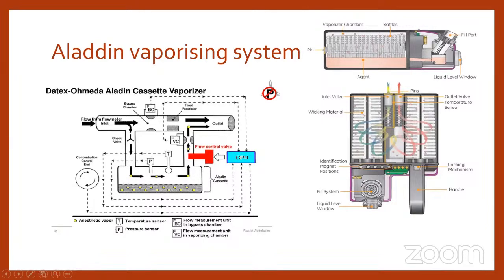It is also a bypass type of vaporizer. The fresh gas comes from the inlet and is divided into two pathways. One is for the vaporizing chamber, and the second one is the direct pathway. The vaporizing pathway goes into the vaporizing chamber, where it mixes with the liquid agent present in the reservoir, and the vapor that comes out of the vaporizing chamber is controlled by the CPU with the input of our system.